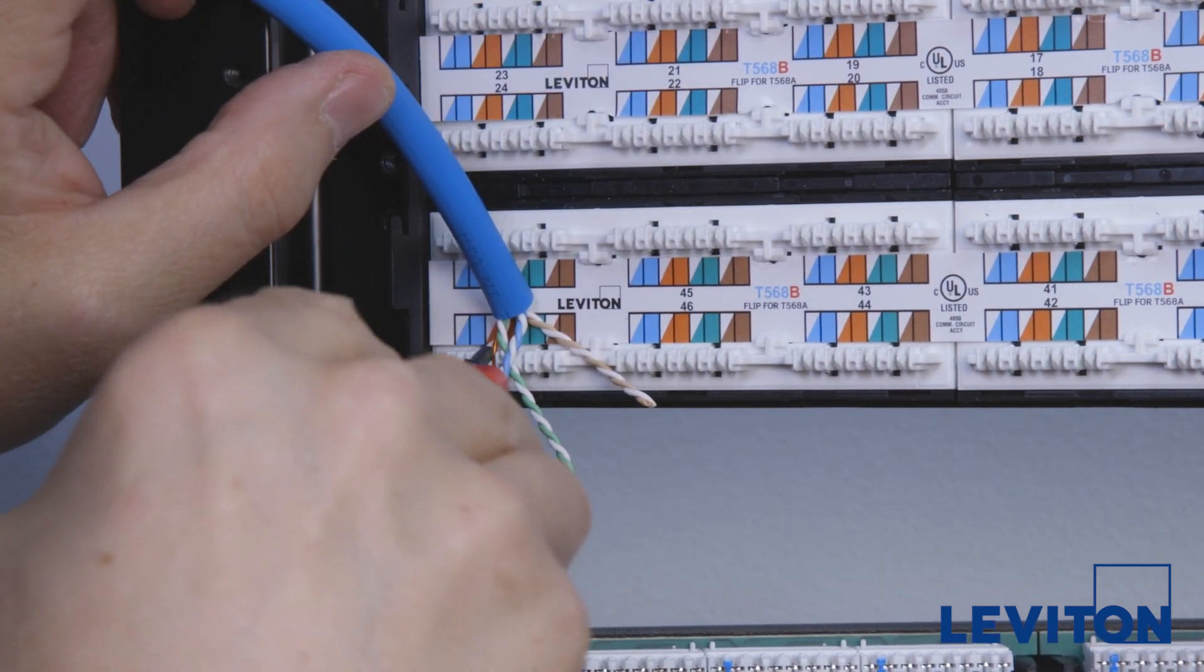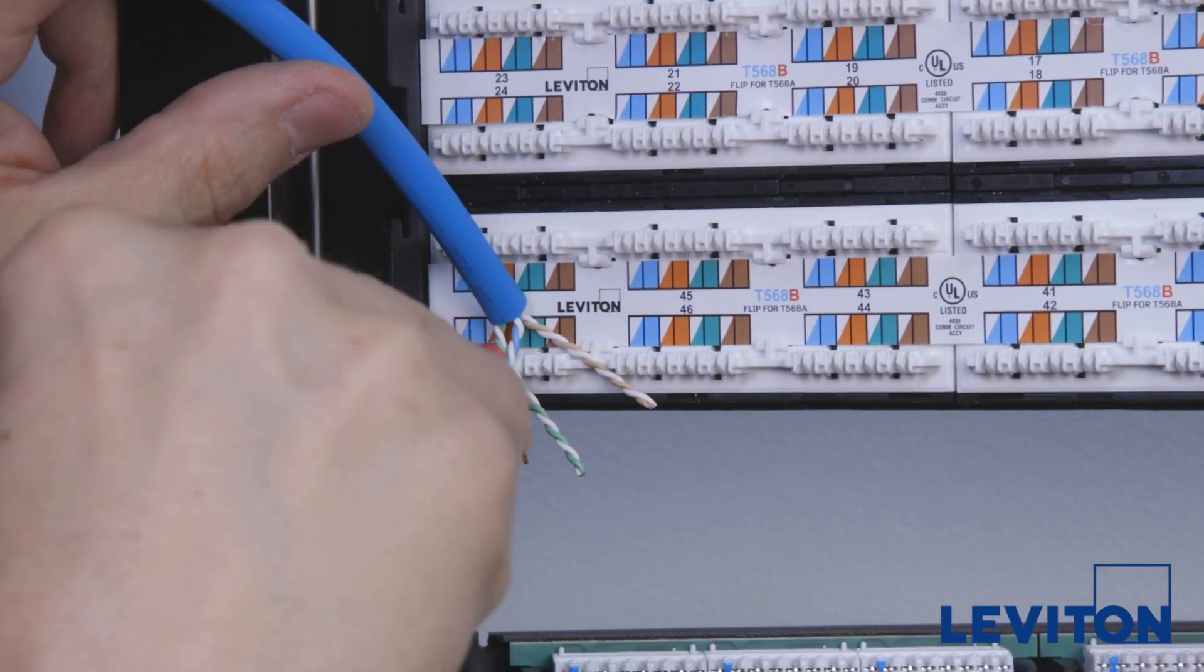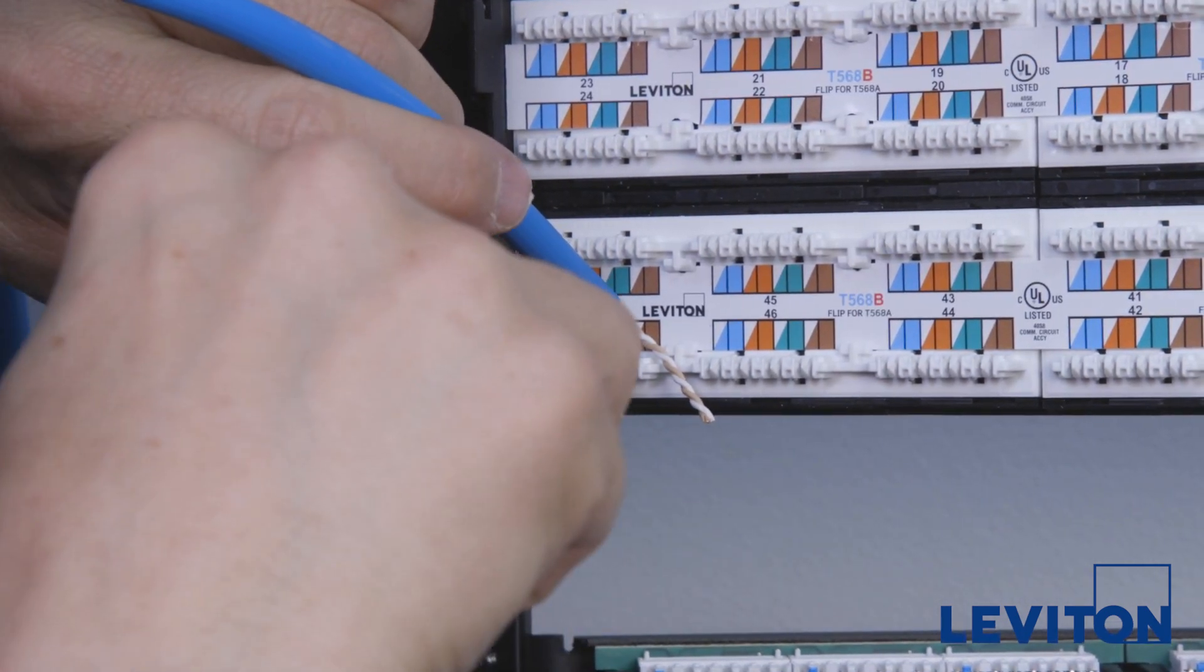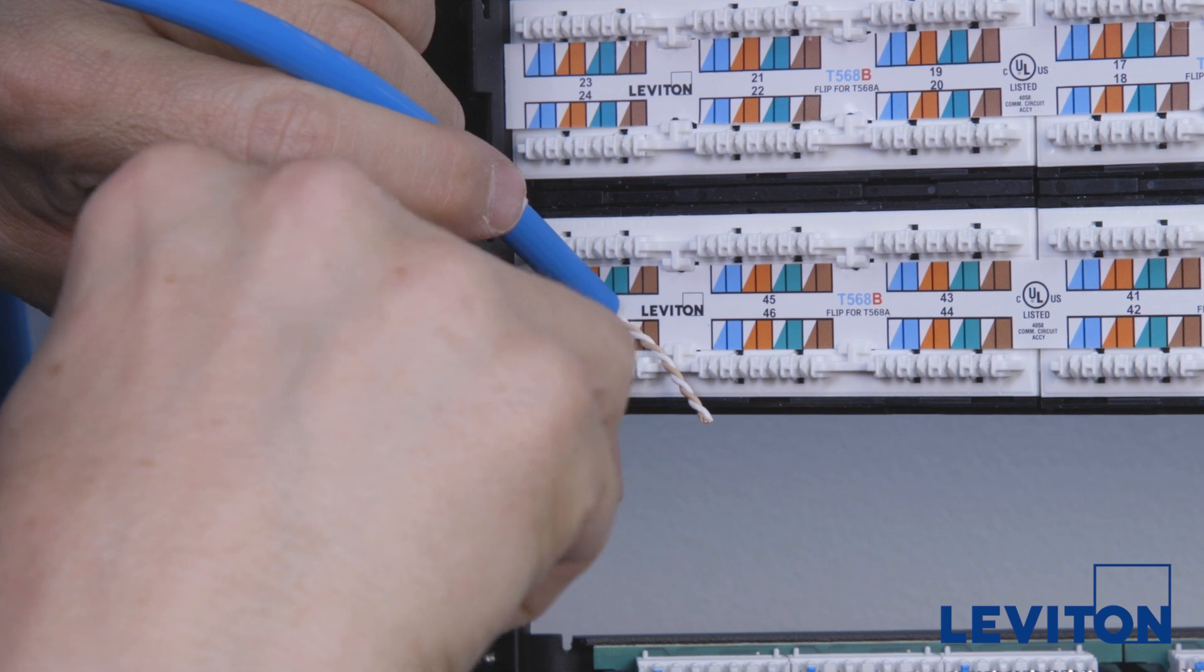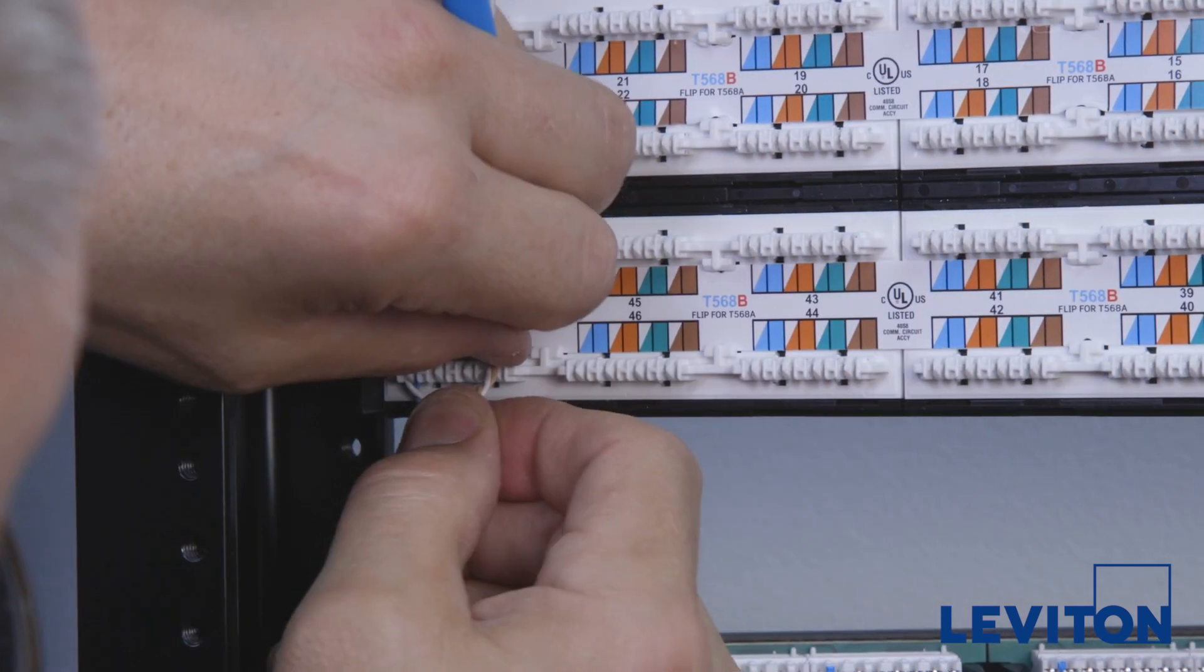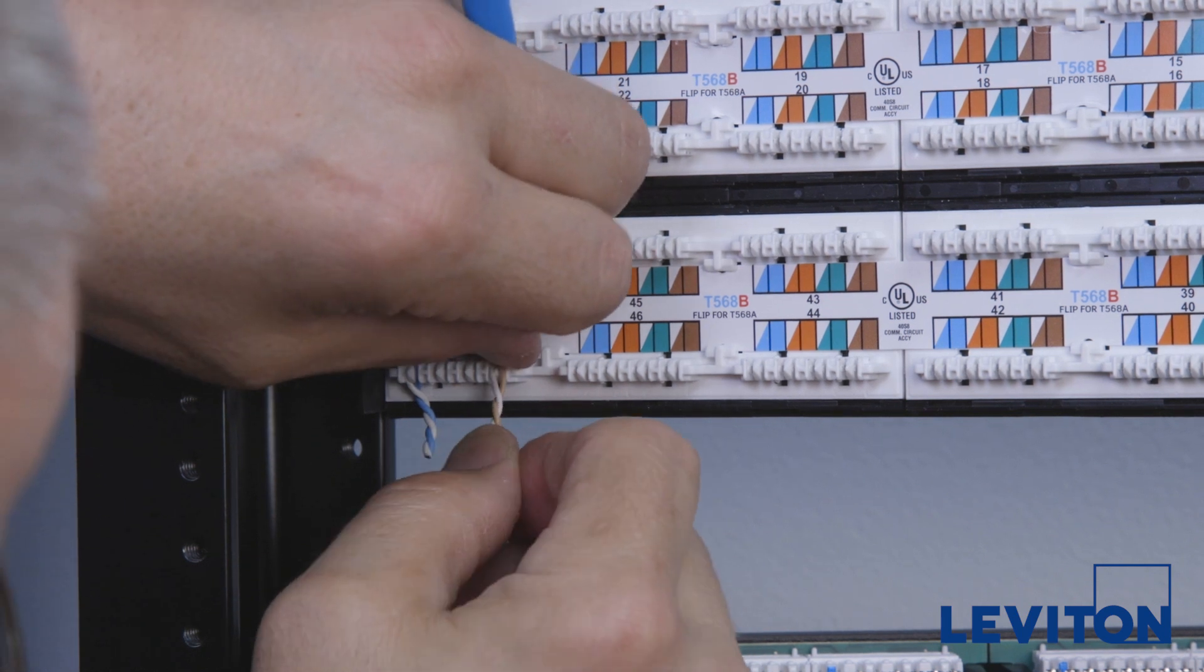Once correctly seated, punch down the pairs using a punch tool set to the low impact setting. Remember that the cut side of the punch tool must face down so that the excess end of the wire below the IDC is cut, rather than inside toward the cable jacket.